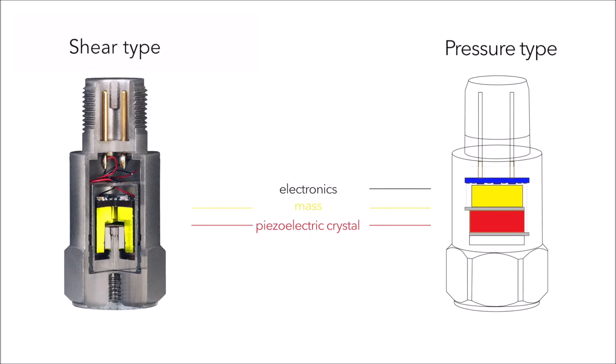The electric charge is transferred into the electronics of the sensor where the electric charge is converted to voltage. This voltage is then transferred into your vibration meter through the sensor connector and cable. In other words, the sensor is shaking on the running machine. The preloaded mass is deforming the piezoelectric crystal and this generates a voltage signal on the output of the sensor.